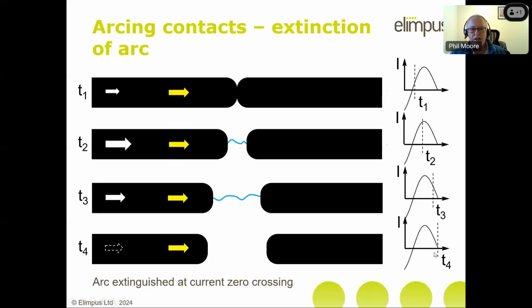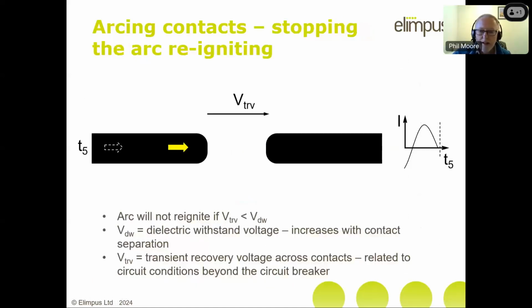the end of it. Now, in reality, actually getting rid of the arc isn't particularly difficult in a circuit breaker. What is difficult is stopping the arc from coming back, and we talk about reigniting the arc. So if you imagine these contacts are now a reasonable distance apart, there are two voltages you need to understand. One is called the dielectric withstand voltage, and that's the voltage that the circuit breaker will tolerate without the arc restriking. And then across that there's the system induced voltage, which is called the transient recovery voltage, and that's not particularly to do with the circuit breaker, that's related to the external circuit. And in the case of a shunt reactor, this gives quite a difficult situation for the circuit breaker.